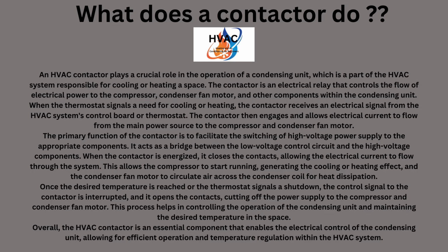When the thermostat signals a need for cooling or heating, the contactor receives an electrical signal from the HVAC system control board or thermostat. The contactor then engages and allows electrical current to flow from the main power source to the compressor, the condenser, and the fan motor. Its primary function is to facilitate the switching of high voltage power to the components when the contactor is energized. It closes the contacts, allowing the electric current to flow through the system. This allows the compressor to start running and generate the cooling or heating effect, and the condenser fan motor to circulate air across the condenser coil for heat dissipation.